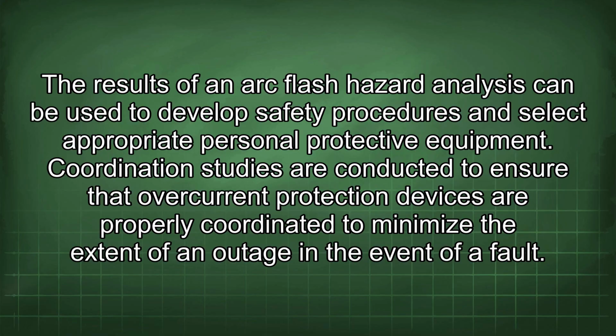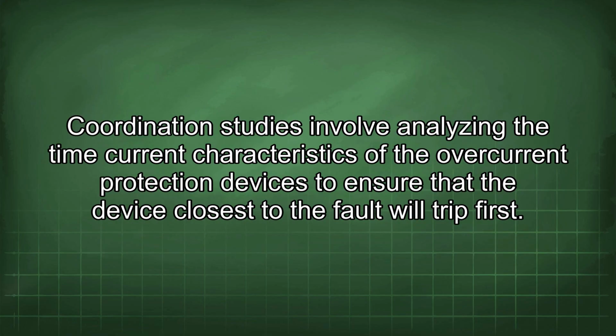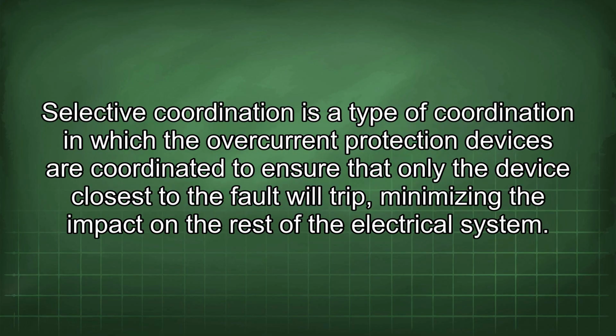Coordination studies are conducted to ensure that overcurrent protection devices are properly coordinated to minimize the extent of an outage in the event of a fault. Coordination studies involve analyzing the time current characteristics of the overcurrent protection devices to ensure that the device closest to the fault will trip first. Selective coordination is a type of coordination in which the overcurrent protection devices are coordinated to ensure that only the device closest to the fault will trip, minimizing the impact on the rest of the electrical system.